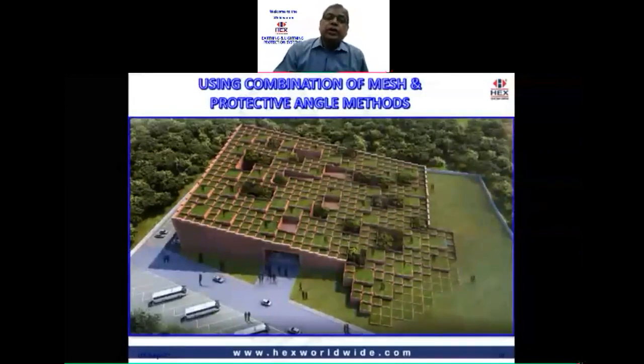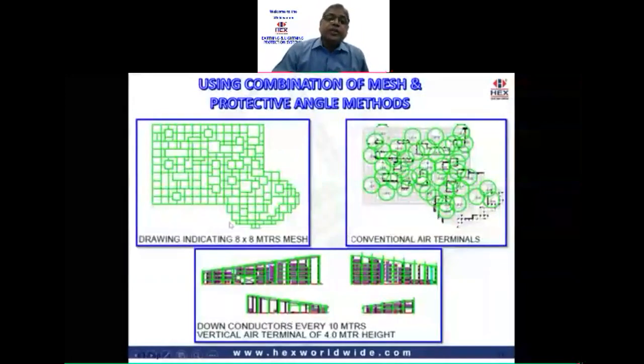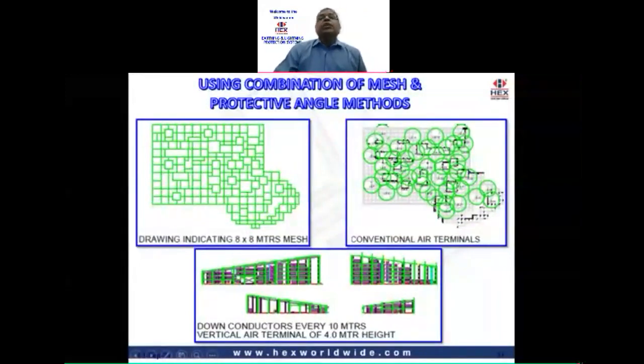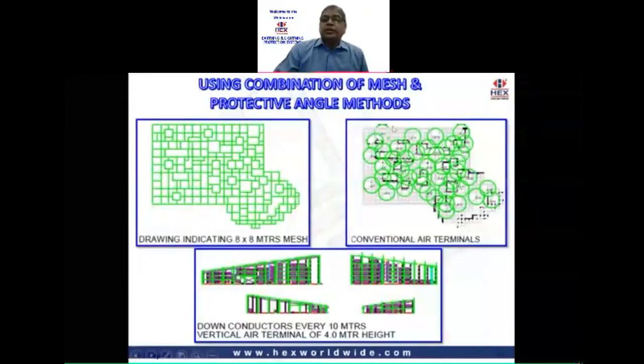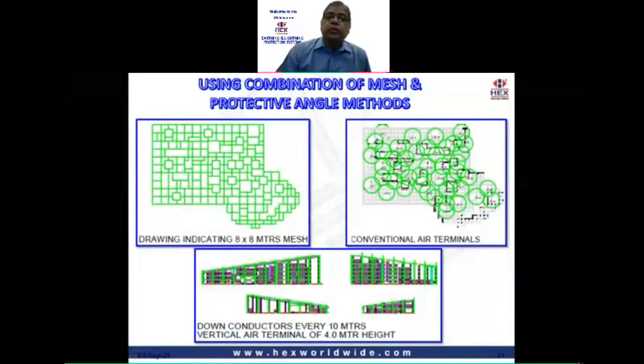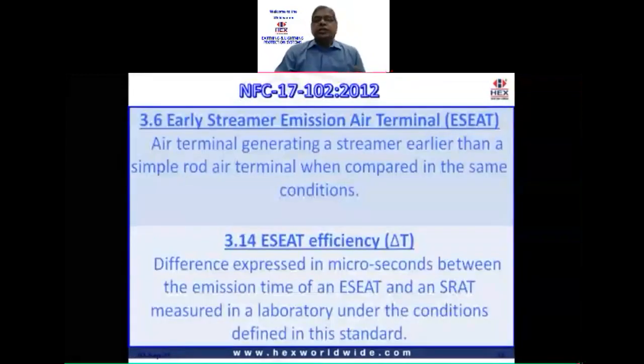We had to use the mesh method, where the whole structure was covered with a mesh of 8 by 8 meters. And we also used the protective angle method, where we had to use, I think, about 44 to 50 conventional lightning arrestors. And everywhere there were down conductors coming down. So you can use these methods in combination to design your lightning protection system. This is what we do. That was about the conventional lightning arrestors.